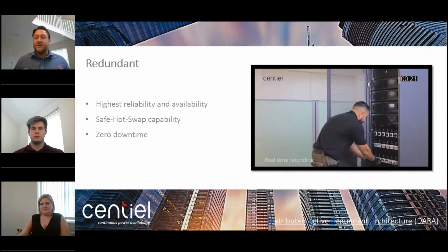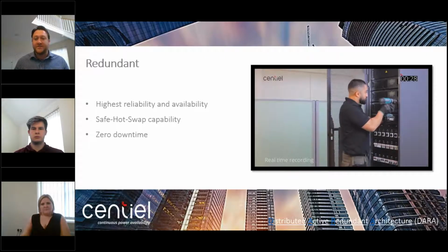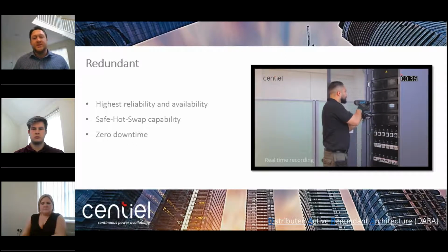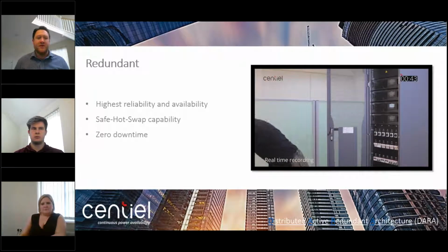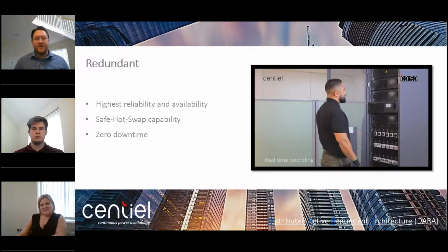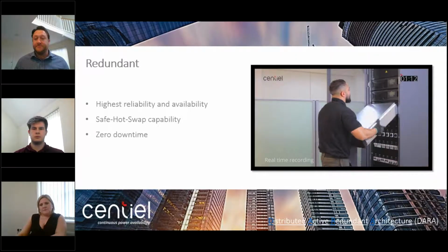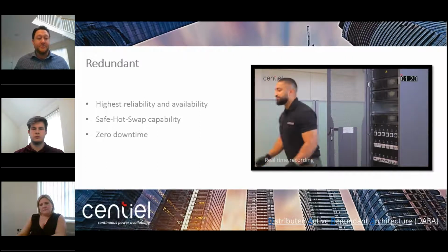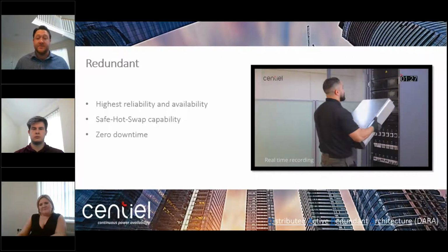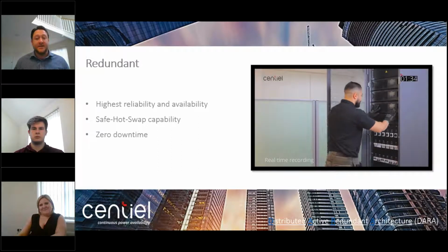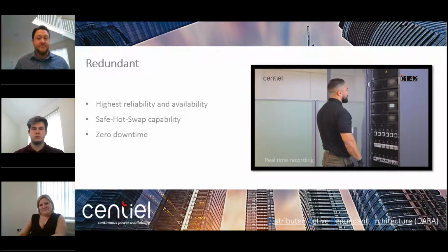Flexible to a point where we can safely and hot live on a system swap a module. So the days are gone where you have a monolithic block UPS, there's a fault on site, and an engineer is called and has to take apart the UPS and diagnose the problem. We now simply turn up to site, exchange a module while the rest of the system is running and supporting the load, access the service module, put it into the system.